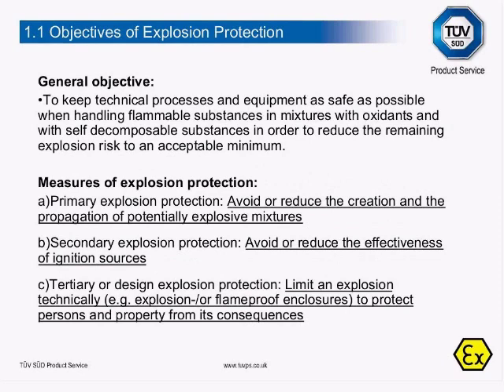The General Objective is to keep technical processes and equipment as safe as possible when handling flammable substances in mixtures with oxidants and self-decomposable substances, in order to reduce the remaining explosion risk to an acceptable minimum. The Measures of Explosion Protection include Primary Explosion Protection: avoid or reduce the creation and propagation of potentially explosive mixtures. Secondary Explosion Protection: avoid or reduce the effectiveness of ignition sources. And Tertiary or Design Explosion Protection: limit an explosion technically via explosion flame-proof enclosures to protect persons and property from its consequences.